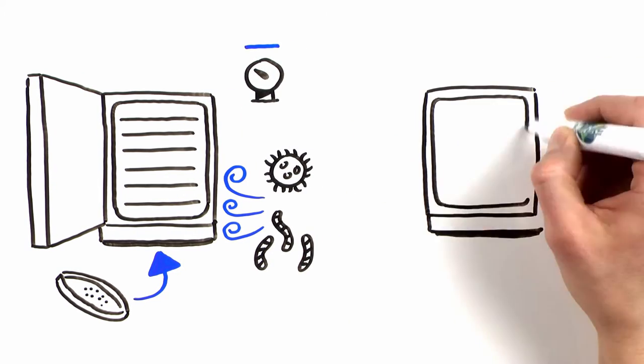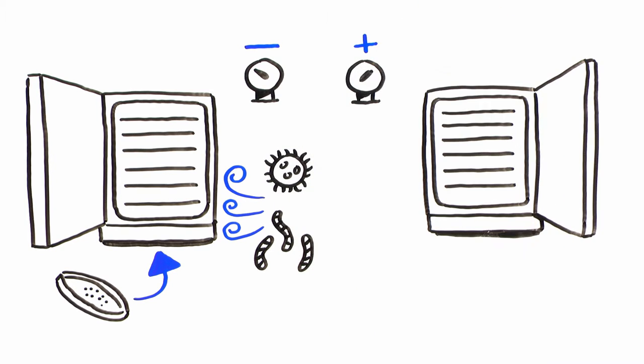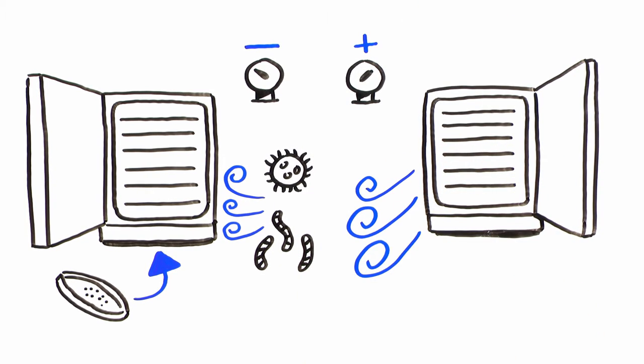New Air maintains the chamber at positive pressure. Sterile chamber air is released into the laboratory upon a door opening, instead of contaminated laboratory air entering the chamber.